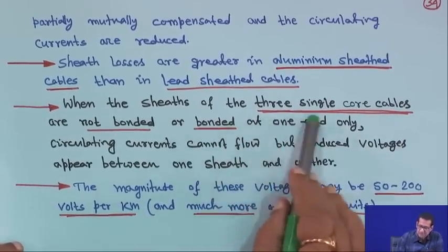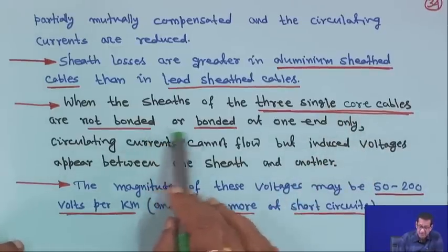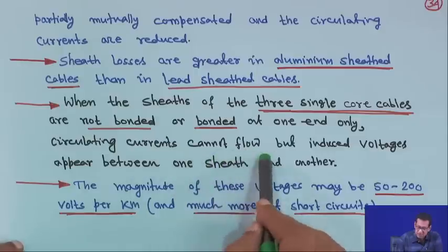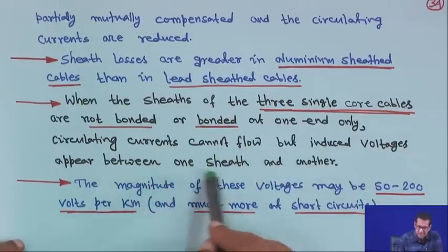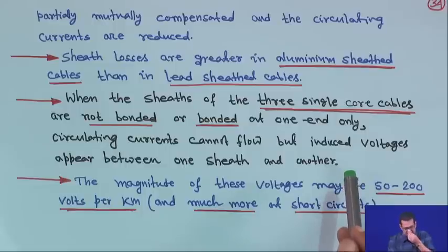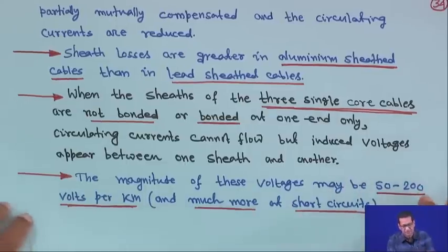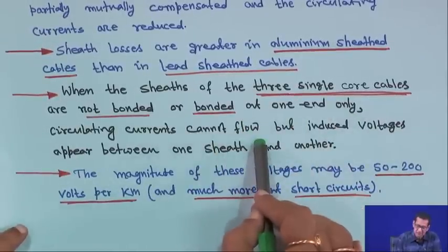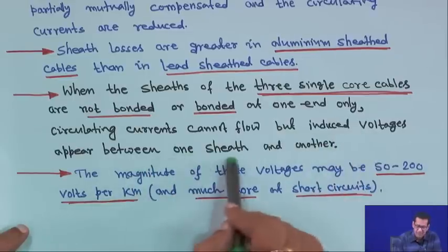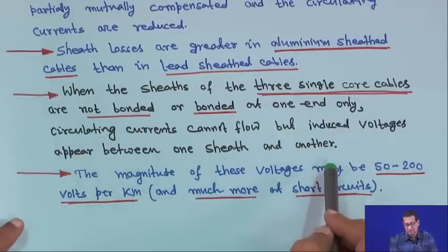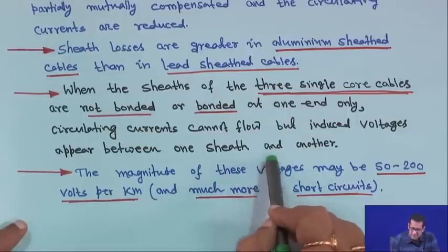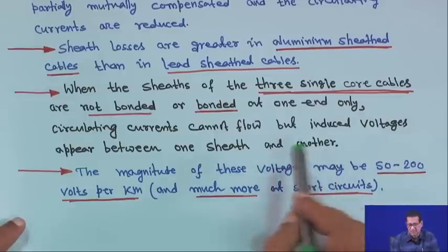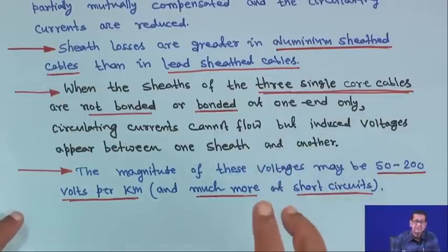When the sheaths of the 3 single core cables are not bonded or are bonded at one end only, circulating currents cannot flow, but induced voltages appear between one sheath and another. For 3 single core cables, this voltage will appear between one sheath and another.